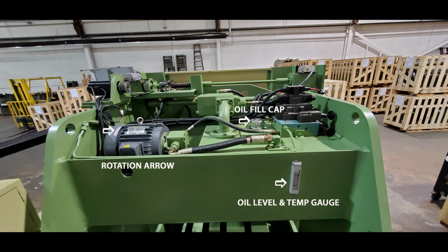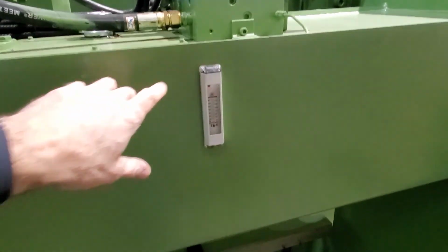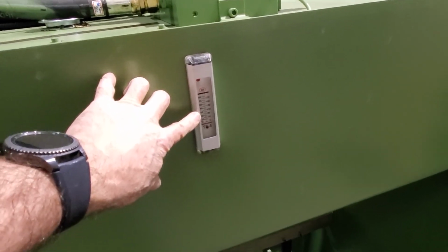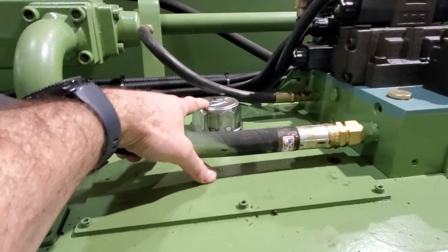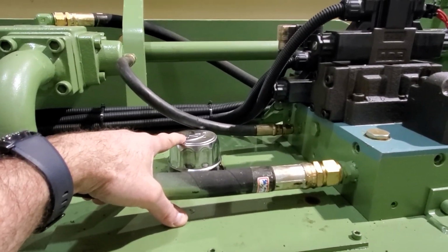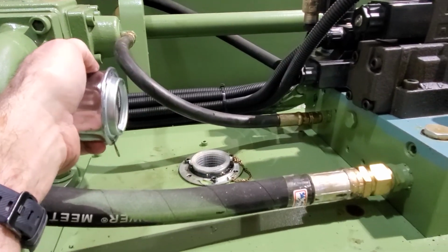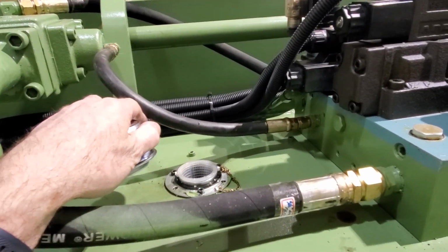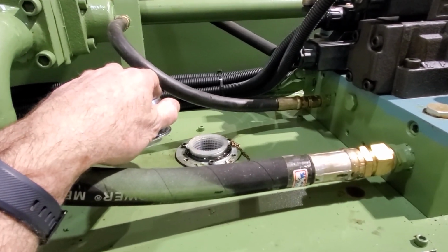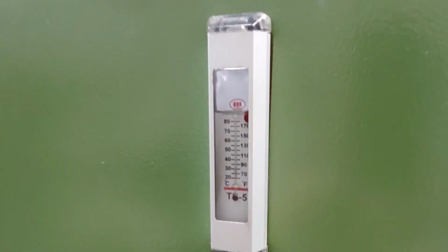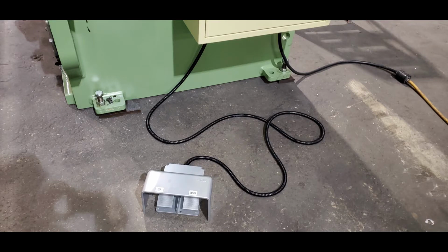Now for the oiling section of this setup, we're going to want to work off the top of the machine here and note the three positions: the oil level temperature gauge, the oil fill cap, and you want to note the rotation. Here's your oil fill gauge, and here's your quarter turn fill cap. You're also going to want to note the capacity in your manual. You're going to need anywhere between 25 and 60 gallons of 68 type oil. And again, double check your oil fill. You should be at 90% on your gauge.